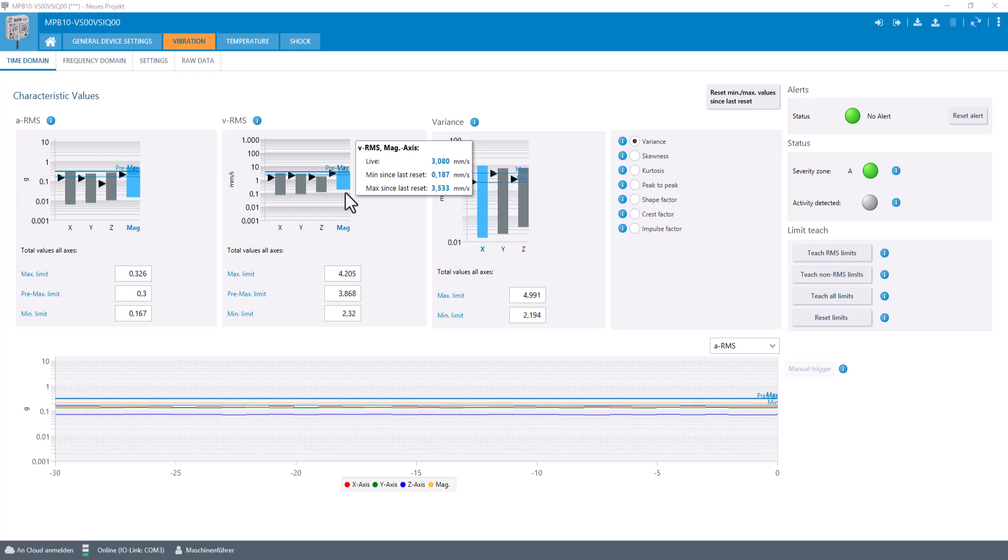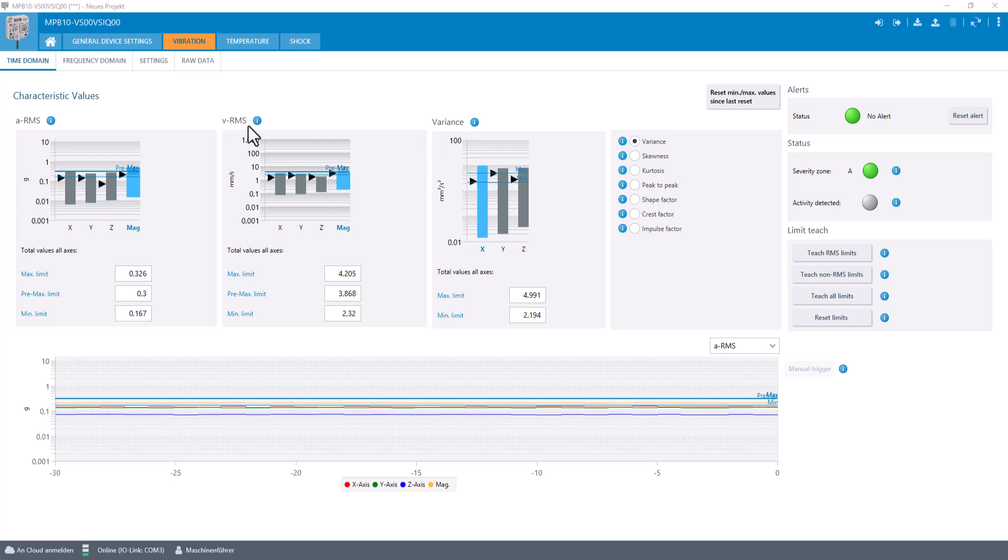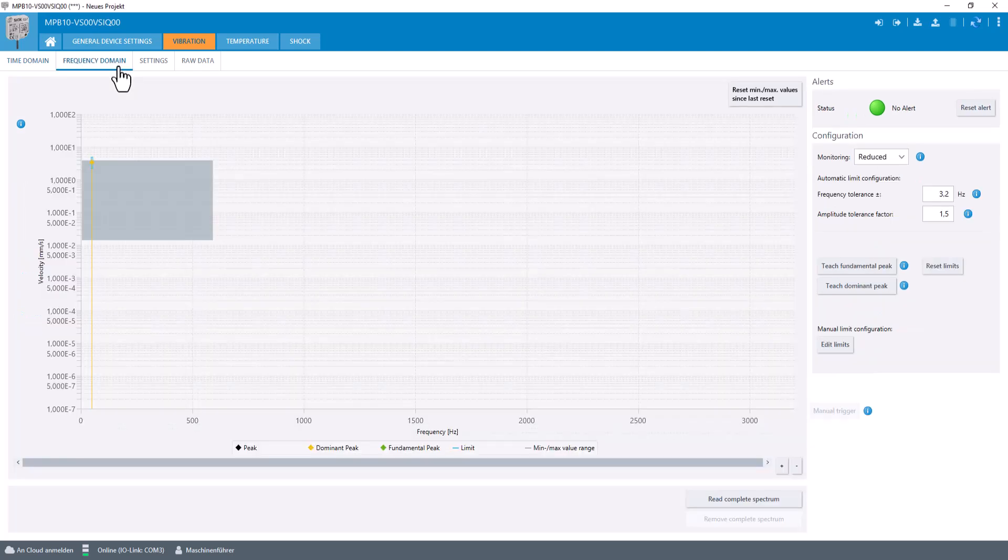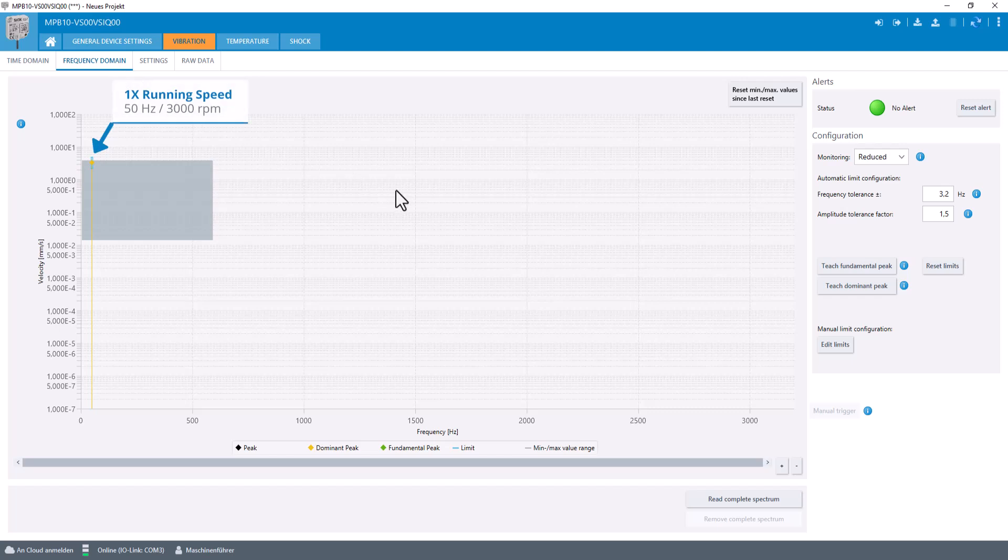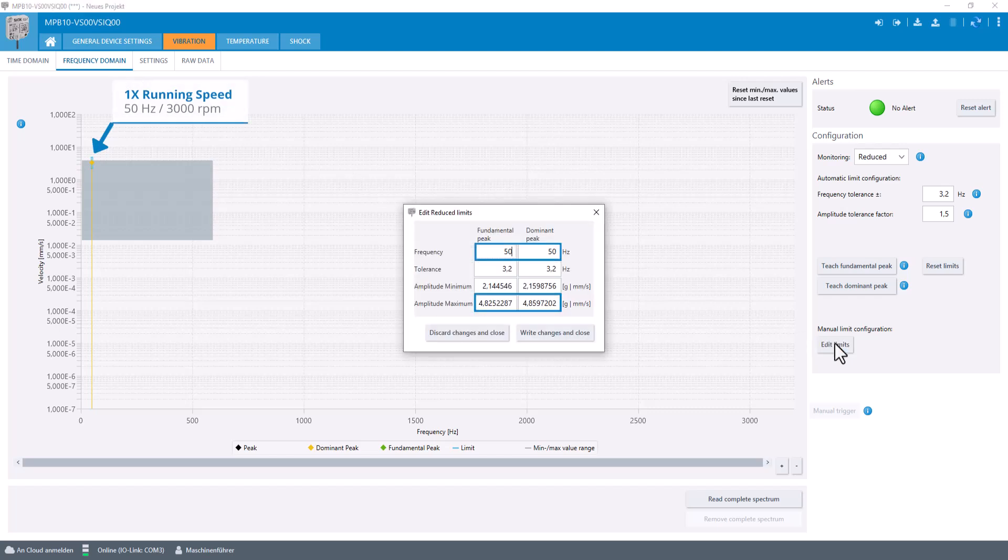Additionally, by looking at the frequency domain, we can monitor the running speed, so-called 1x. This peak is expected at 50 Hz, which represents the 3000 RPM.